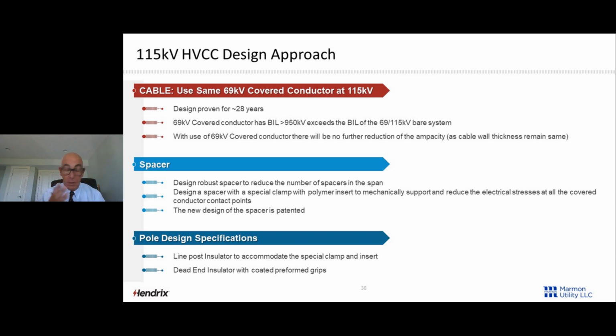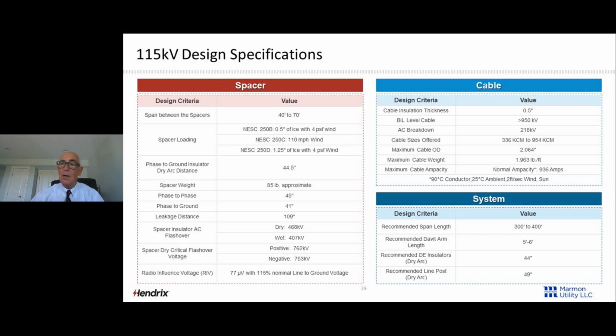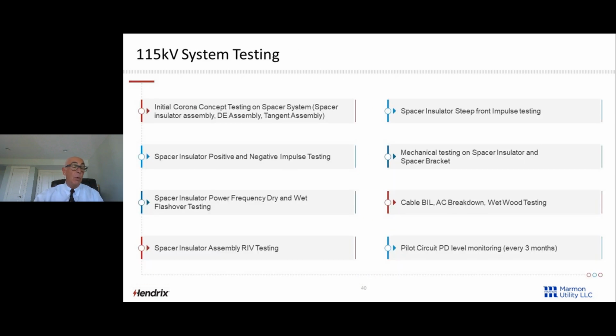The spacer is massively different, and for the pole design specs, you've got to run your calculations and see what kind of pole you need. Again, the spacer is very different. We'll take a look at that. Instead of 30 feet between spacers, now we're going 50 feet between spacers. We say 40 to 70, but we're recommending 50. That spacer weight is no longer a couple of pounds. It's more like 85 pounds, so that's getting heavy. The cable is the same cable we used at 69 kV. We've been involved with testing this 115 kV system for as much as 15, 20 years.